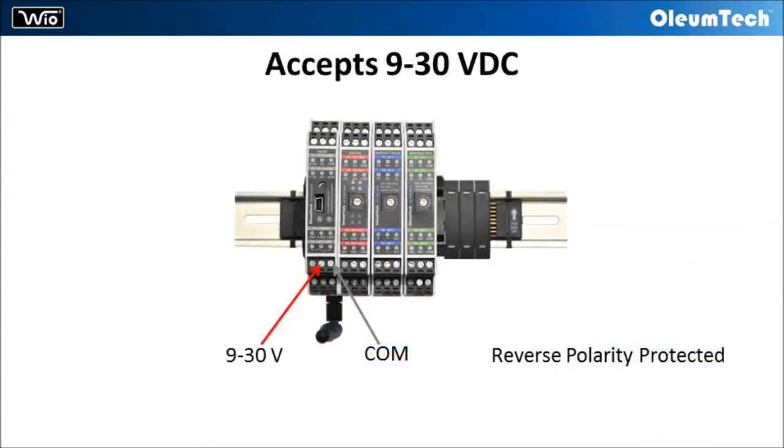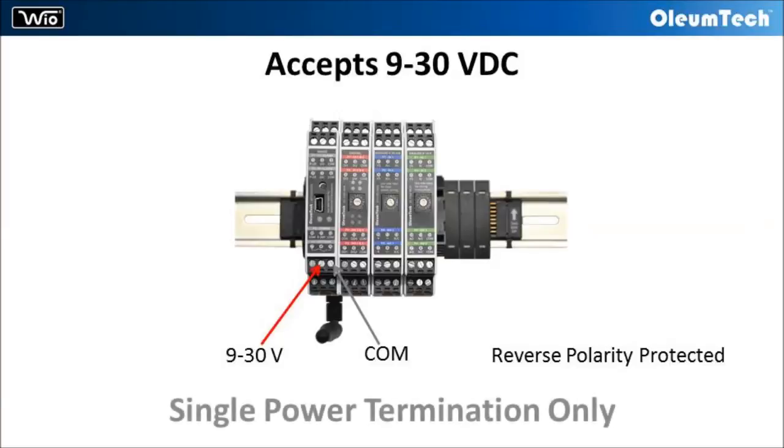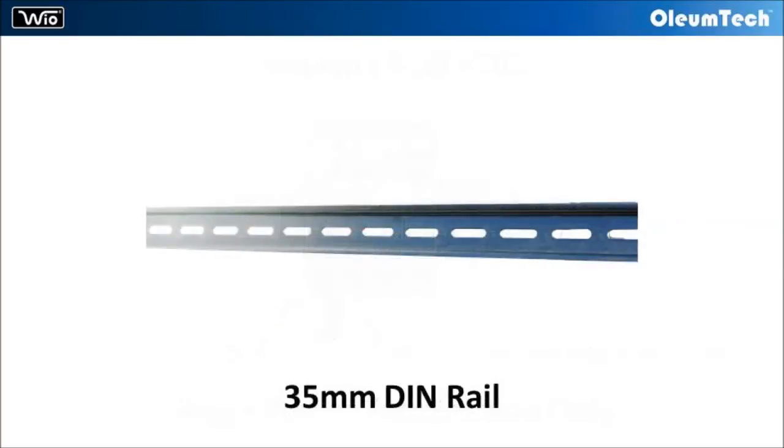The Wio system can operate using 9 to 30 volt DC. The radio module supplies power to the connected I/O modules, so only a single point power termination is required.